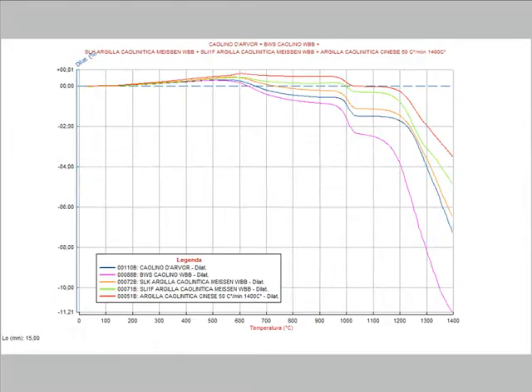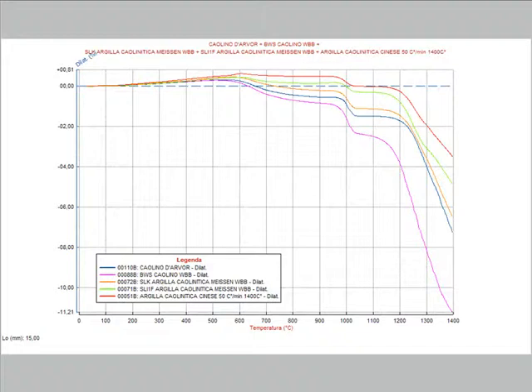One of the favorite field of application of the optical dilatometer MISURA-HT is the control of the thermal behavior of ceramic raw materials. This is a comparison between several kaolinitic clays carried out with the heating rate of 50 degrees per minute up to 1400 degrees centigrade.